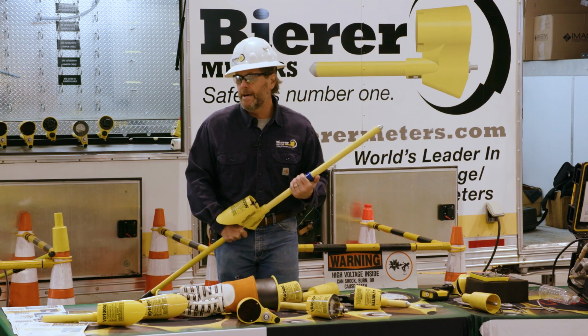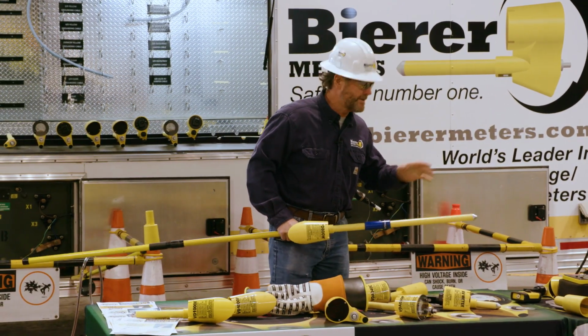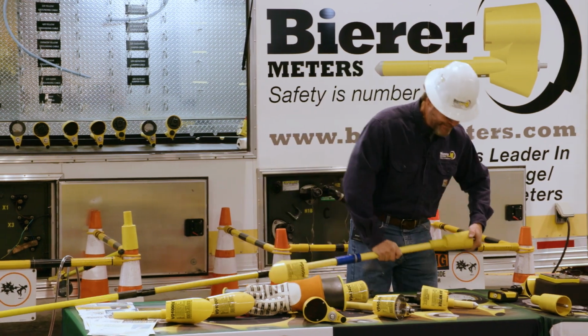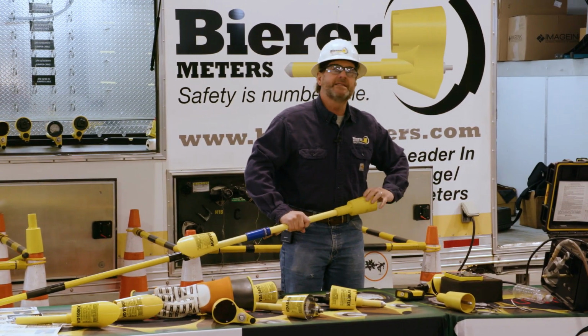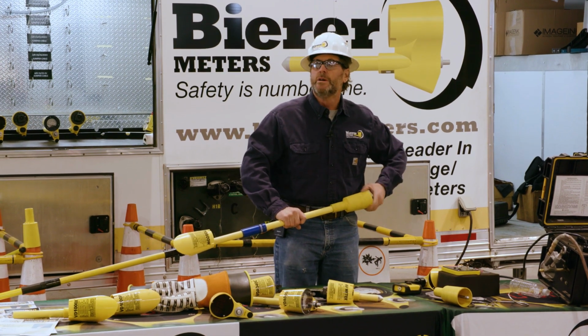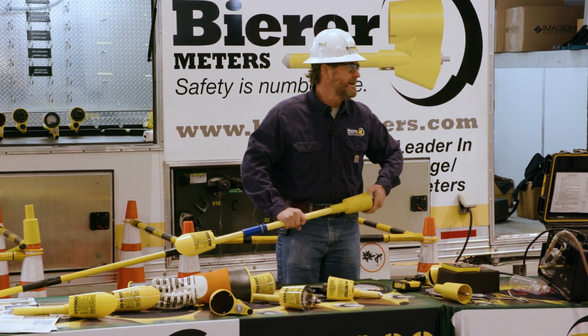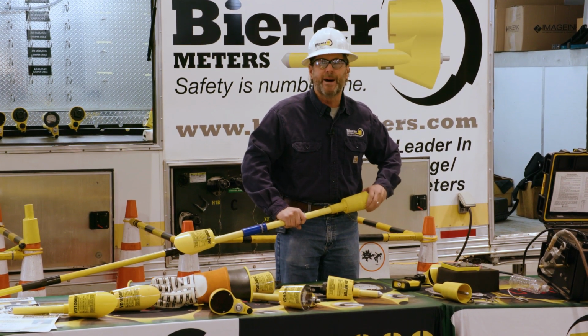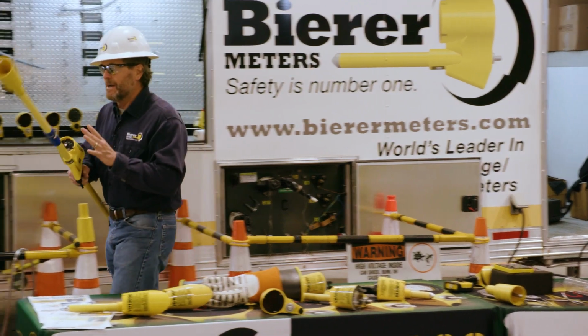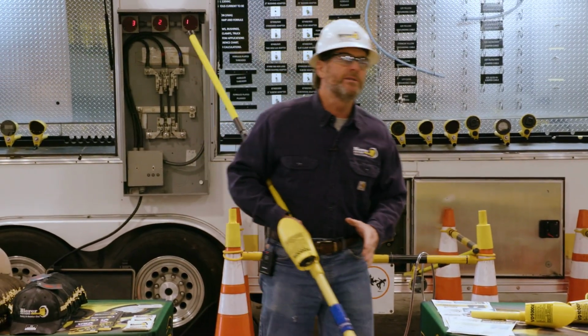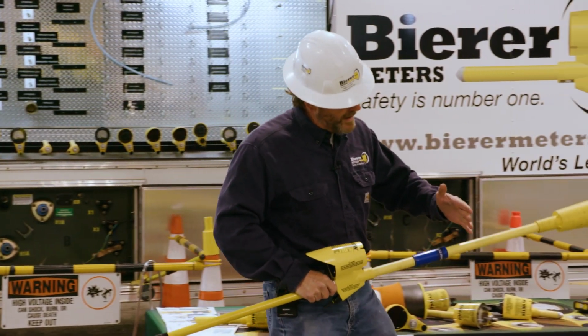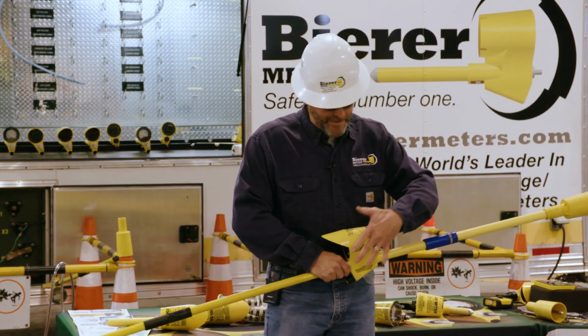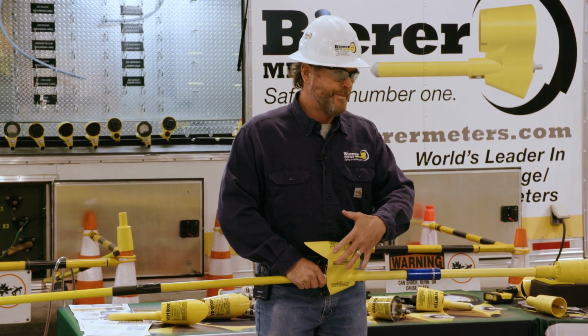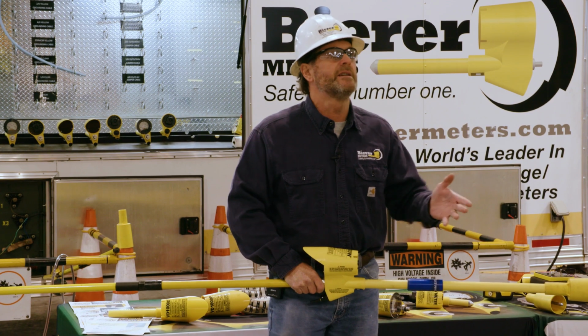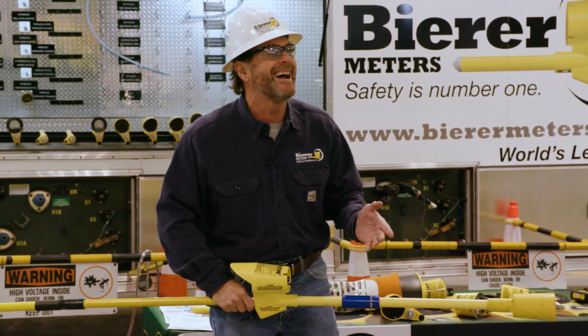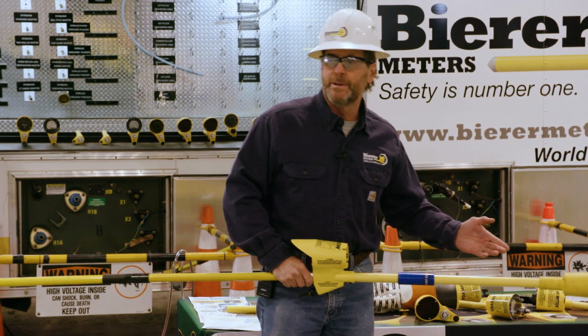So what we're going to talk about: there's going to be situations where you visually inspect your work area, and using your phasing tool, your voltage indicator, corded or wireless, you find an issue—a cabinet close by, a bleed wire nearby. Maybe you're doing a substation, and if you make contact with the conductor, there might be another hot phase near the meter head. You don't want that situation because the opportunity for an arc flash is very high.